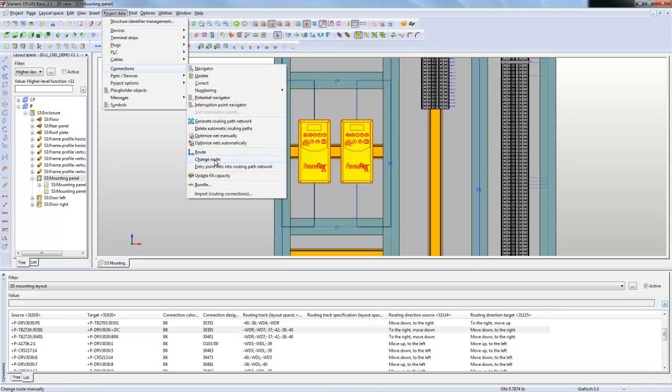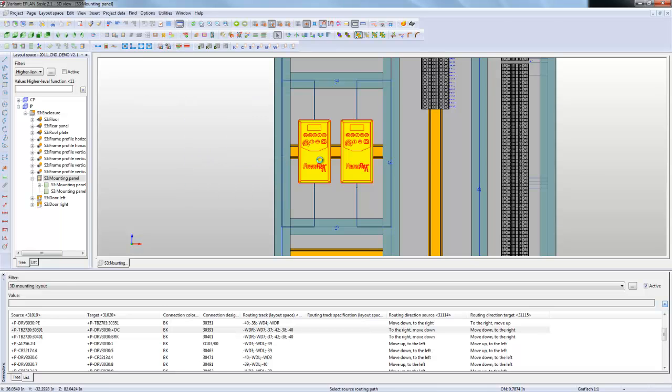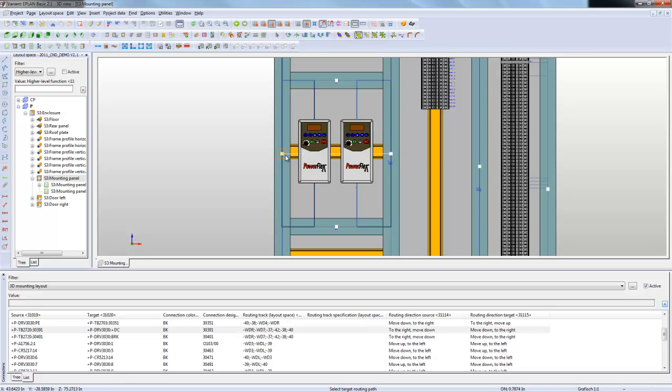One thing that you have here on the project data connections is change route. I'm going to pick it and it's going to give you all these routing points. I'm going to grab this route. Everything that's inside this duct going through this section right here, I'm going to click and bring it over here to the left hand side. I want it to route everything by the left hand side.